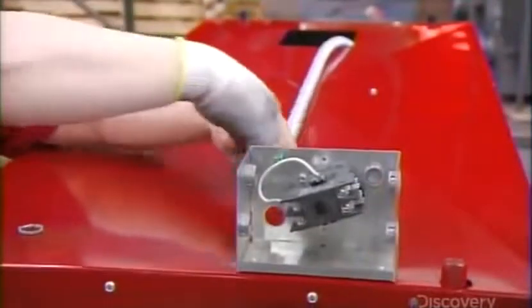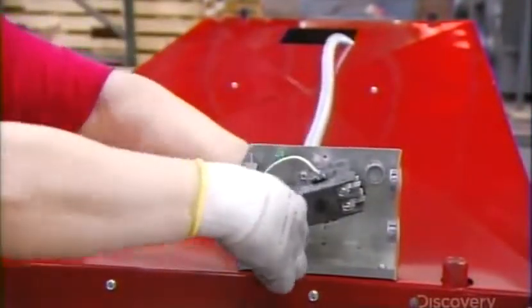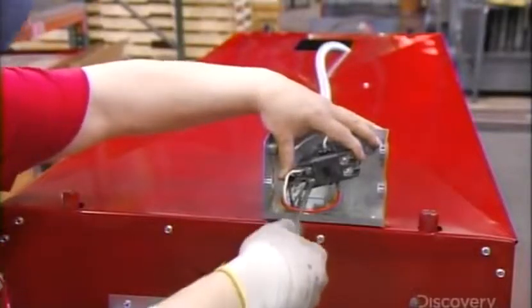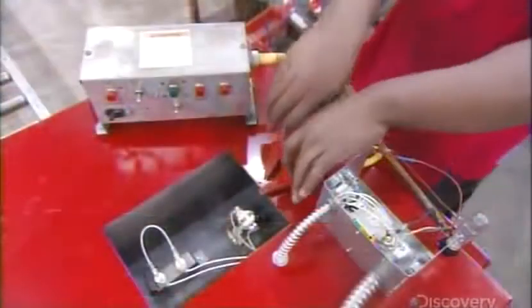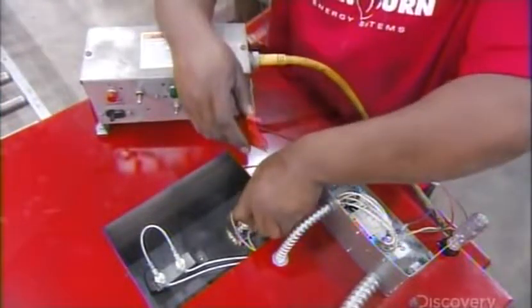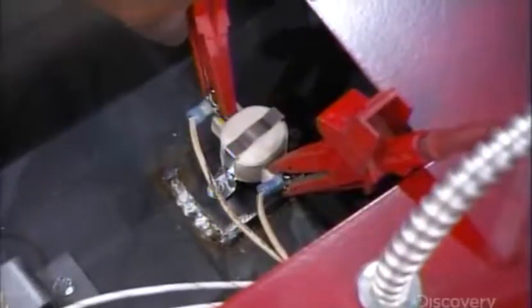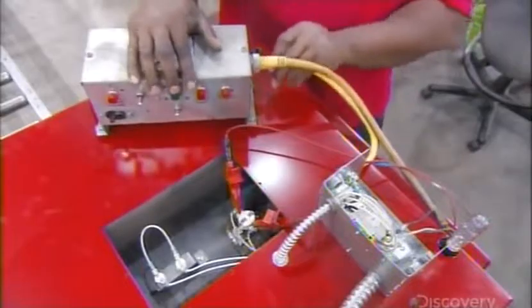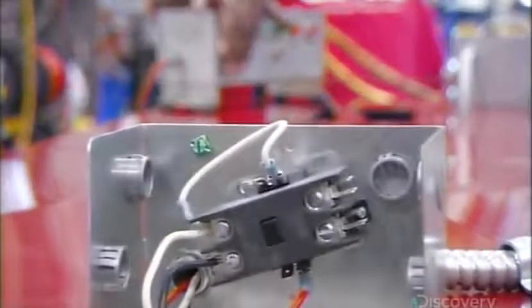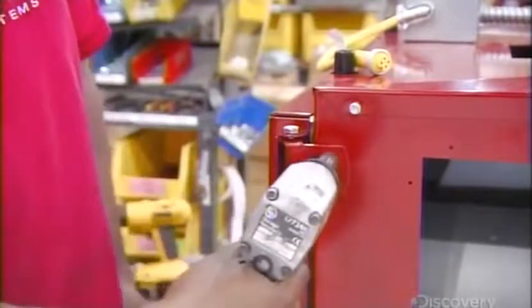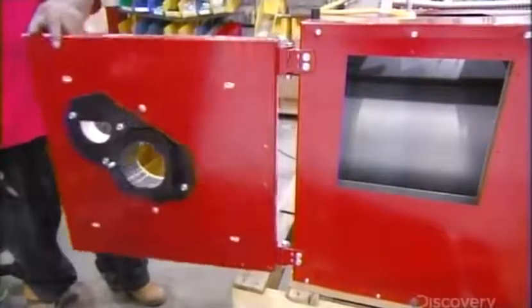Now he hooks up a blower control box. This electrical box regulates when hot air is sent into a room. A worker then connects a tester box to the temperature controls that measure the temperature inside the furnace. He runs a number of tests to confirm that both the blower and the burner will turn on or off when they're supposed to. He verifies the operation of the door that allows for cleaning out ash residue.